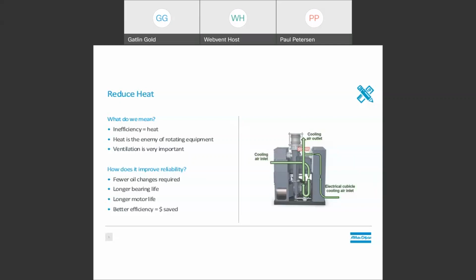Atlas Copco intentionally uses separate air streams for cooling and process air, as shown in this photo of a turbo blower here. The cooling air, this allows you to choose whether to duct the cooling air or to pull it from the room. Depending on your blower building's HVAC, one of those is likely a better choice than the other. More importantly, all hot exhaust is rejected out of a single separate cooling grate on each machine. This allows you to duct that hot exhaust out of the room in summer. If you add a manual or thermostatically controlled louver to that ducting, then rejected heat can be diverted back into the room to provide makeup heat in winter.